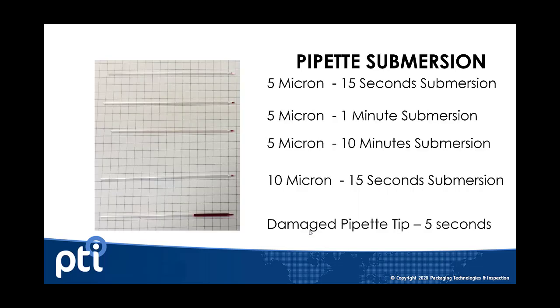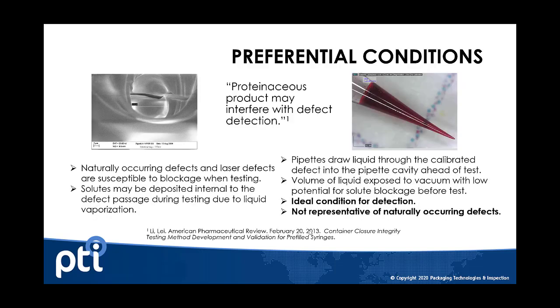You can see different defect types and how the liquid gets drawn up into the pipette to create that opportunity to be vaporized for easy leak detection. We do not recommend the use of pipettes or capillaries for these applications. A proteinaceous product will be easier to detect when simulating that defect using a pipette, and in that case the pipette is not an ideal condition for validating a test method — it's not representative of the true defects that are produced.